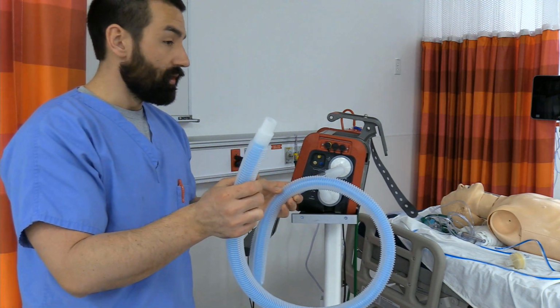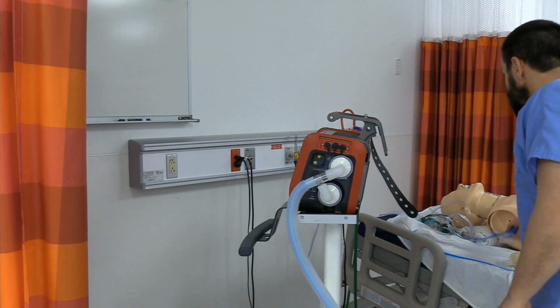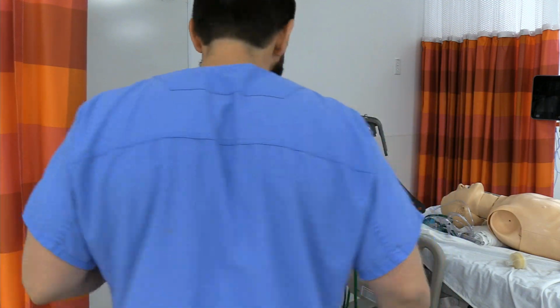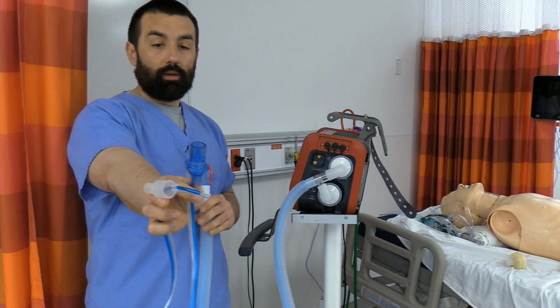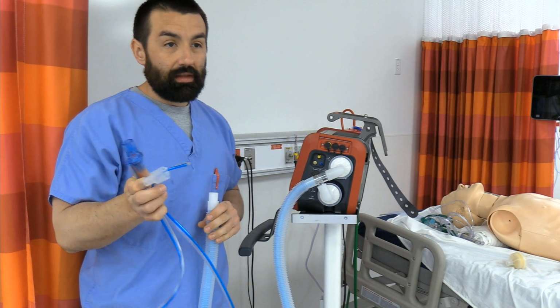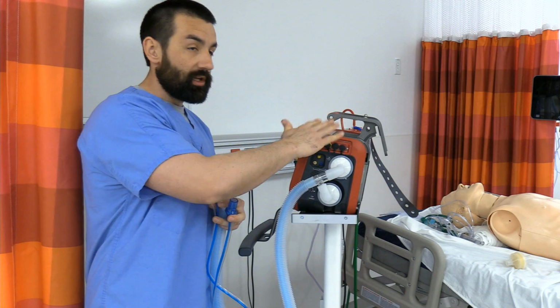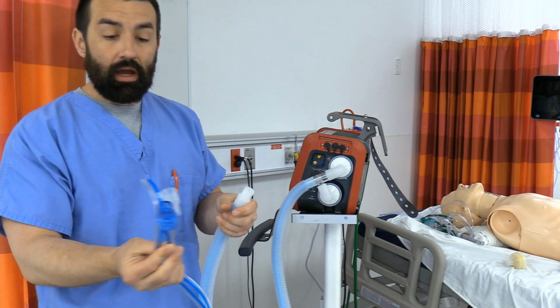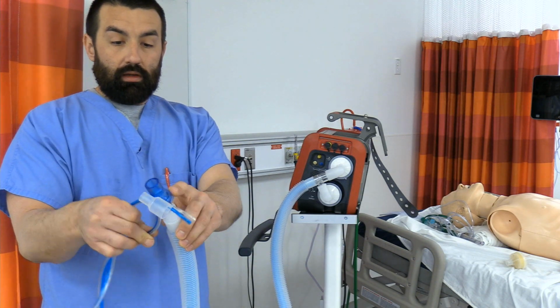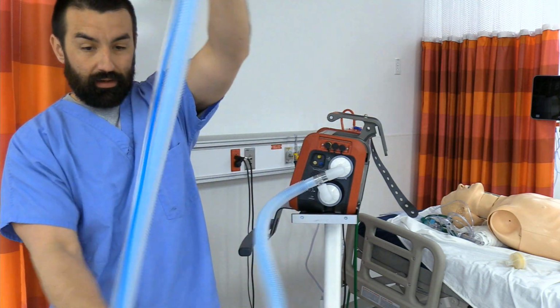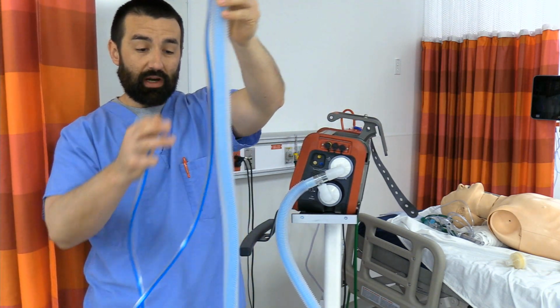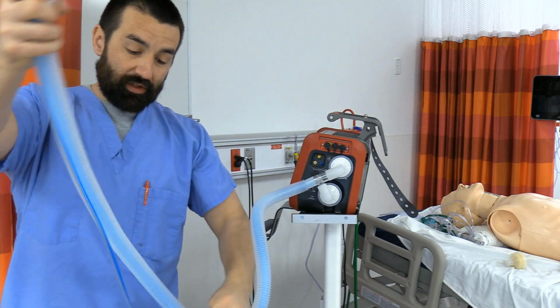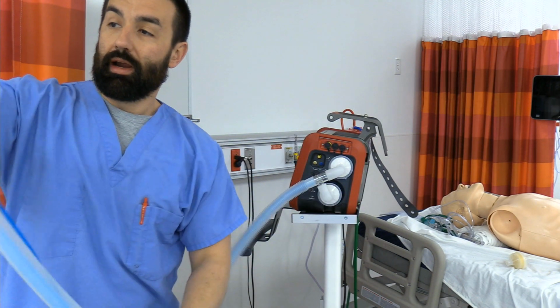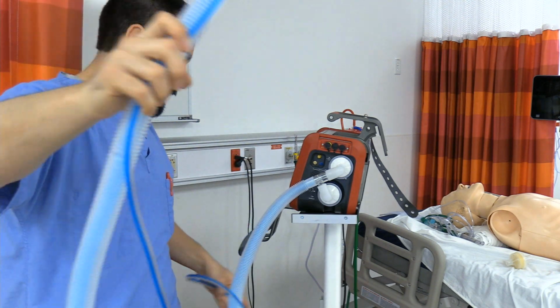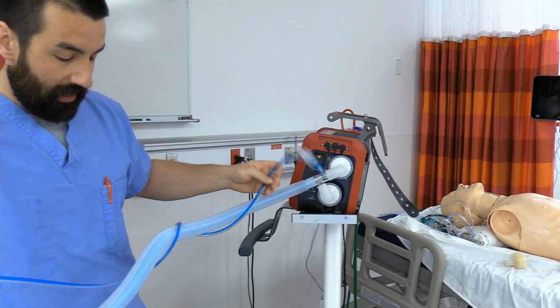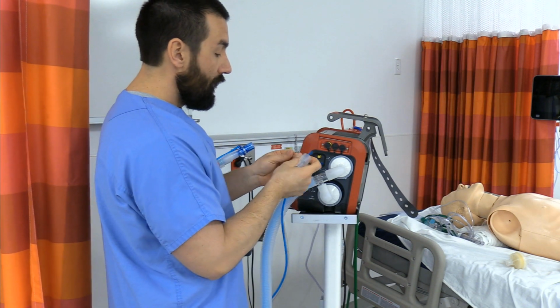We got to add on a flow sensor and talk about humidification here though. So, as already mentioned, the Hamilton vents are the only ones that are routinely using a proximal flow sensor for invasive and non-invasive ventilation and such. Most of the other ventilators, the flow sensing is going to be happening on the expiratory side as the air goes back to the vent. So our flow sensor, disposable, all right, going to go right there. I've used the circuit pretty hard. Usually there's a bunch of clips. I'd recommend locking your flow sensor around the circuit, especially if we're going on a transport, not just staying here in the lab, just because if the flow sensor cords are all over the place and it's unhinged, you're more likely to get a big tangle and get something disconnected.